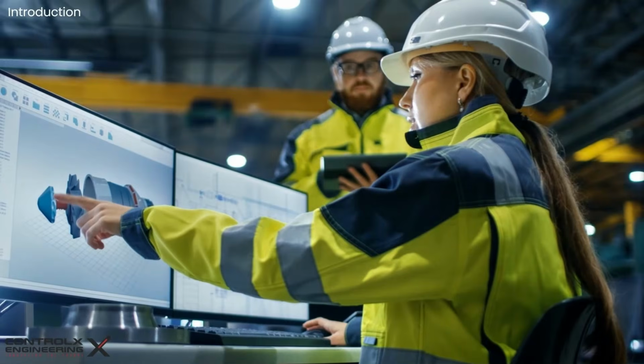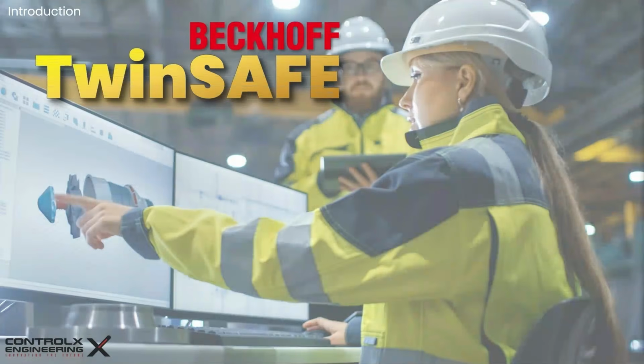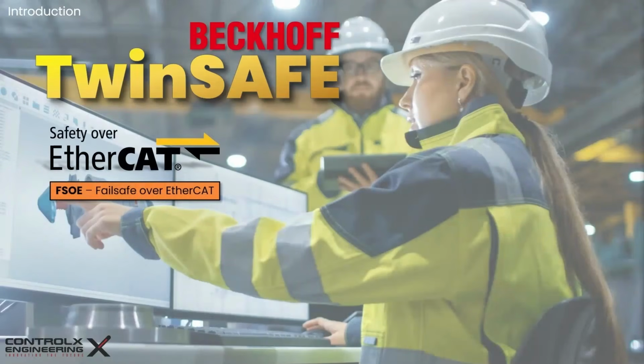Programming safety logic shouldn't be a headache, and that's where TwinSAFE shines. TwinSAFE is an integrated functional safety solution from Beckhoff Automation that allows us to build complex, fail-safe logic directly within the TwinCAT environment that you're already familiar with. By leveraging the FSoE, or fail-safe over EtherCAT, protocol, TwinSAFE tunnels safety data through your existing EtherCAT network, eliminating unnecessary redundant hardwiring while meeting the highest global safety standards up to SIL 3 and performance level E.